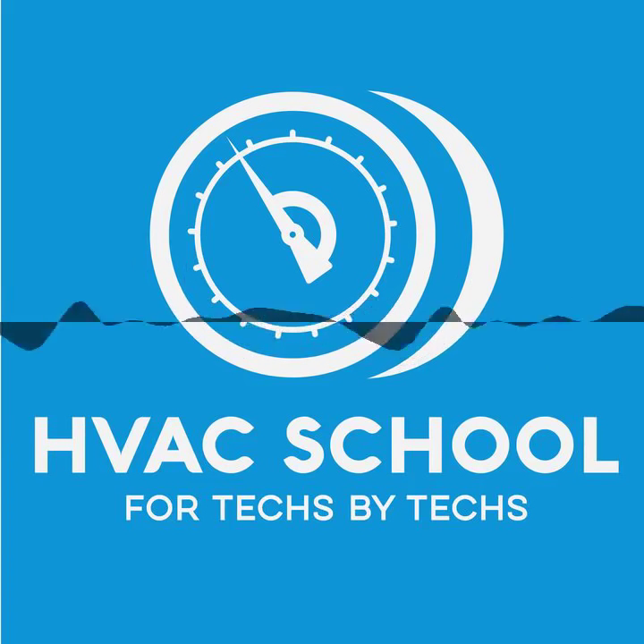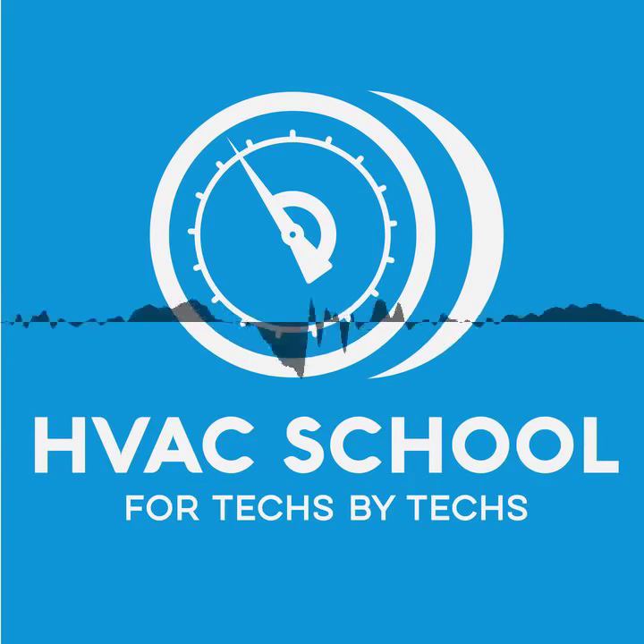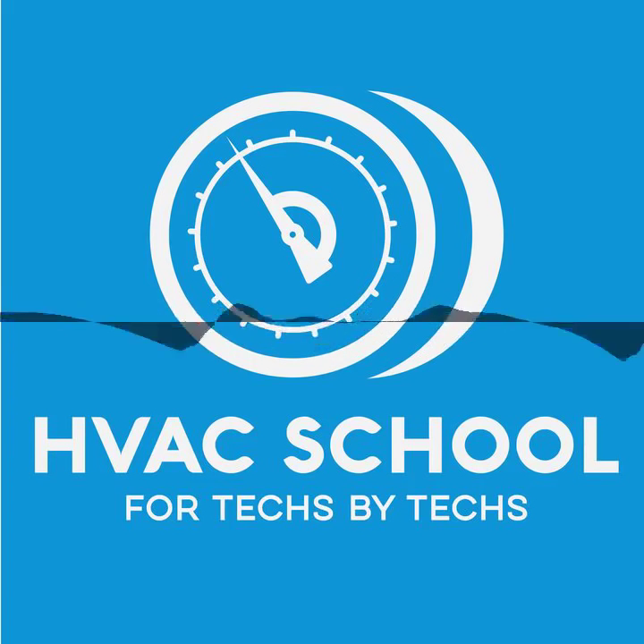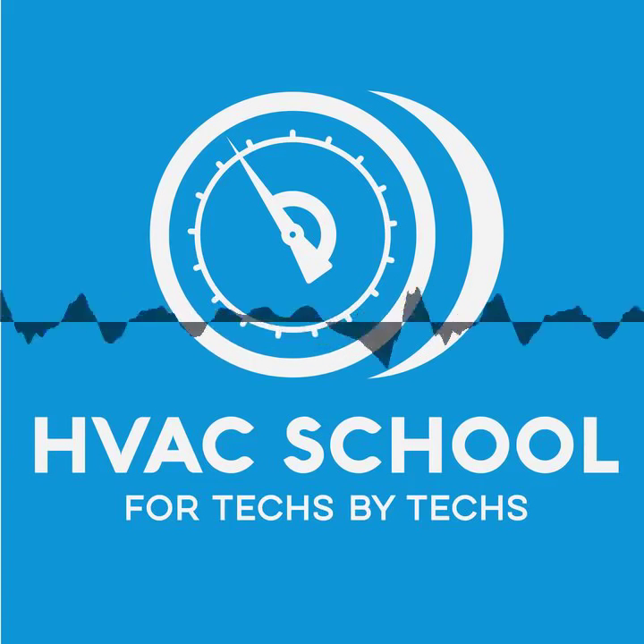Is it always worthless to ohm out contactor coils? No, it's not always worthless. If you have two of the same contactor coils, or you know what the resistance should be in its static state, then that's totally fine. But if I ohmed that out and tried to use Ohm's law to tell me what the amperage would be on that coil, it would be totally wrong.